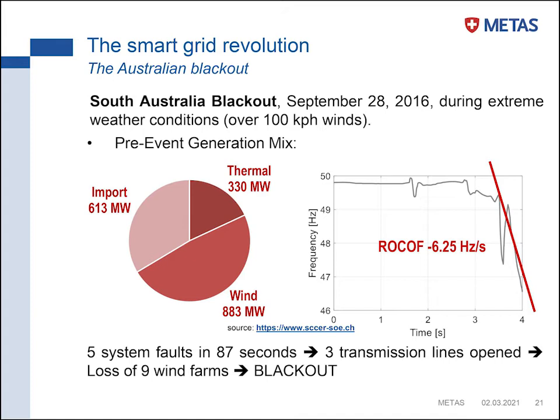If we look at the frequency in the Adelaide area, we can see that it was quite stable. Then when the event occurred, this kind of snowball effect of problems concatenating to other problems produced a huge drop of the frequency, going down by minus 6.25 hertz per second. If you remember, I said the rate of change of frequency should never exceed plus minus 2 hertz per second—here we are more than 3 times that. As soon as we reach 47.5 hertz, there will be a blackout, and in fact an entire part of Australia went into blackout.